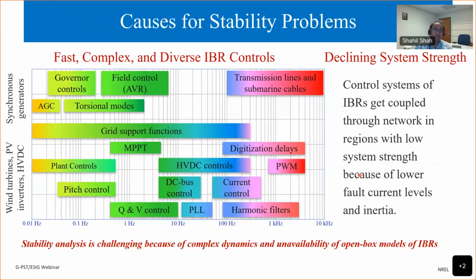Before talking about the tools to understand these oscillations or small signal stability issues, I would like to talk about what the causes are, and why we are seeing them more frequently now. There are two main reasons. One is fast, complex, and diverse IBR controls. Fast means the controls of inverter-based resources span from a fraction of a hertz to a couple of kilohertz. So their bandwidths are all over the place compared to synchronous generators, where the control bandwidths were limited.